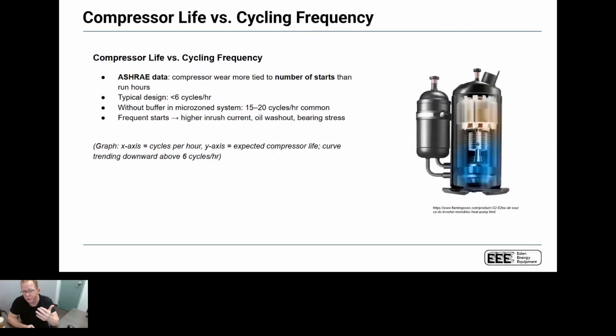Well, what does that mean? Well, what that means is that even if you have an inverter drive, if you don't design your system properly, you can end up in a situation where you have massive, massive cycles per hour. Like you have a situation where a system's coming on and off all the time, and that frequent start-stop will cause issues with that compressor, and that compressor will fail. And that can show up as quickly as 1 year into the heat pump running. And the solution to this is very simple. One, don't run it at 140 degrees if you only need 100-degree water. Understand your application. And two, don't just read something on the internet or come to a 1-hour training session and go, oh, Mike said I don't need a buffer tank.